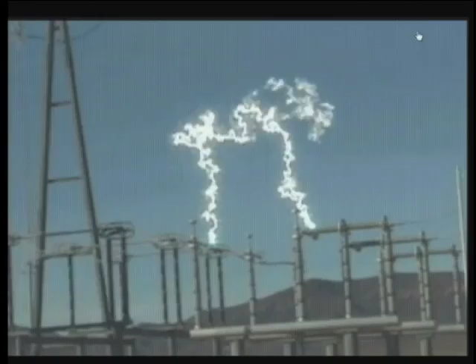It got really bad. This particular failure continued to burn because those protective devices failed to communicate with a neighboring device, in this case because of misconfiguration. Then the second contingency upstream occurred, communication didn't happen, so the backup protection failed, resulting in the tertiary protection having to coordinate and finally clear the fault. There it goes, there goes our power. That was beautiful.